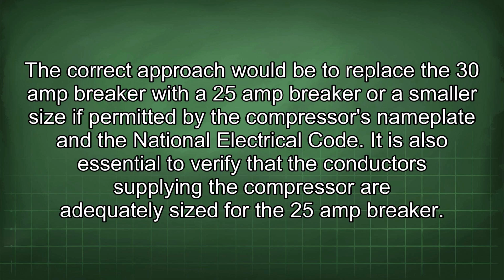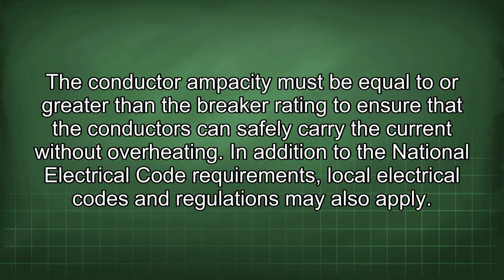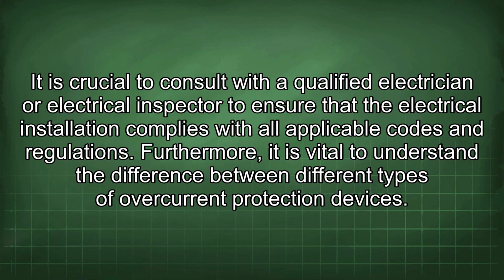It is also essential to verify that the conductors supplying the compressor are adequately sized for the 25 amp breaker. The conductor ampacity must be equal to or greater than the breaker rating to ensure that the conductors can safely carry the current without overheating. In addition to the National Electrical Code requirements, local electrical codes and regulations may also apply. It is crucial to consult with a qualified electrician or electrical inspector to ensure that the electrical installation complies with all applicable codes and regulations.